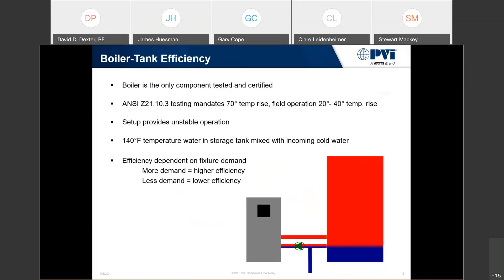The sizing of the pump for that secondary piping is very important. If the heat exchanger's minimum flow is 15 GPM, that pump is pushing 15 GPM constantly — pulling from the tank, pushing through the instantaneous or condensing boiler, and throwing it right back into the tank. If there's only 3 GPM demand in the building, we're only feeding 3 GPM of cold water but still need 15 GPM through the exchanger. The other 12 GPM comes from the storage tank of 140-degree water — so we're mixing 3 GPM cold with 12 GPM hot, meaning we're not feeding the coldest water possible.